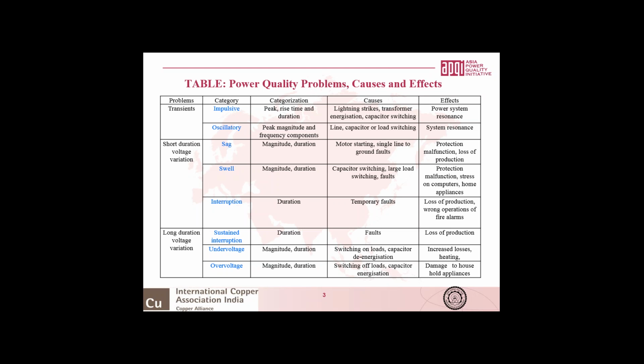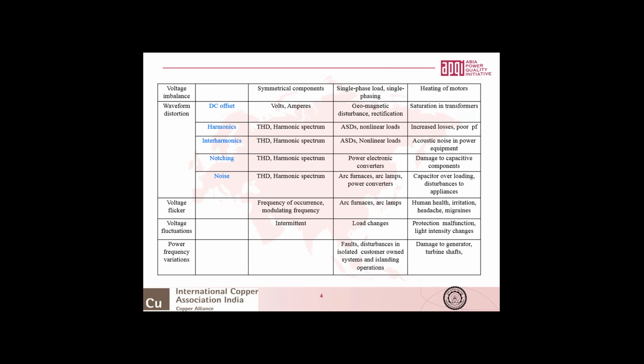If we go to the next slide, we have waveform distortion, which may have DC offset, harmonics, interharmonics, notching, and noise. The first one is of course voltage imbalance. That causes heating, typically of AC motors like induction motors. Even a 1% unbalance in the voltage normally causes 6 to 7% unbalance in the current, because the backward field impedance is quite low, which is 1/6 or 1/7 of the forward impedance. So this amplifies the current, especially in the rotor circuit, and causes heating, especially in the rotor of the squirrel cage induction motor. Similarly, the DC offset causes saturation of the transformer.